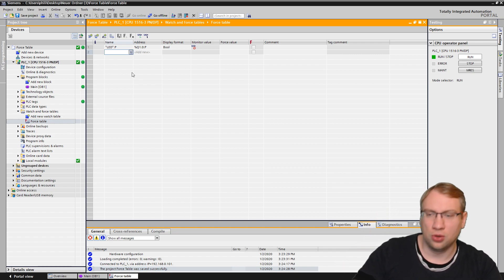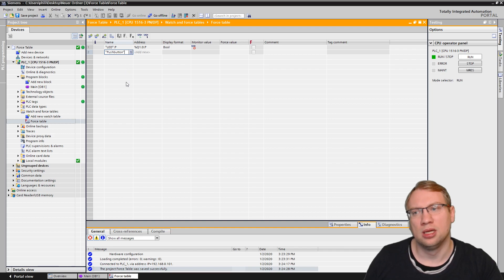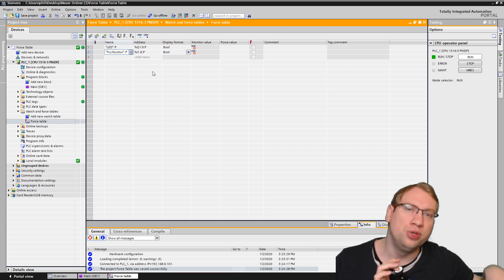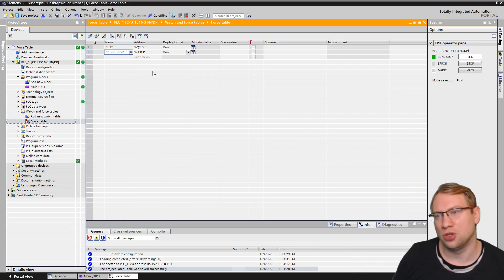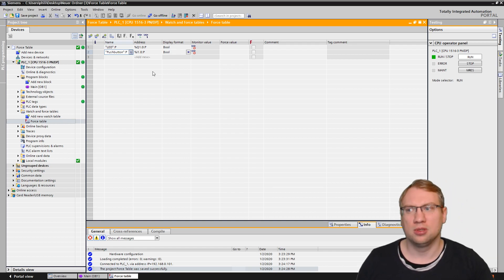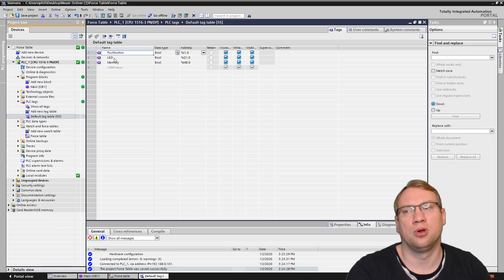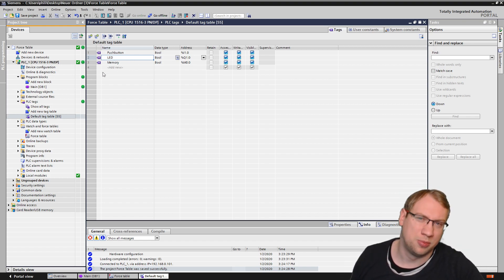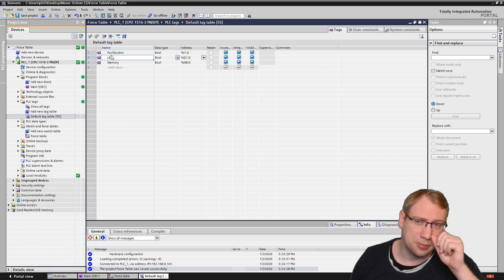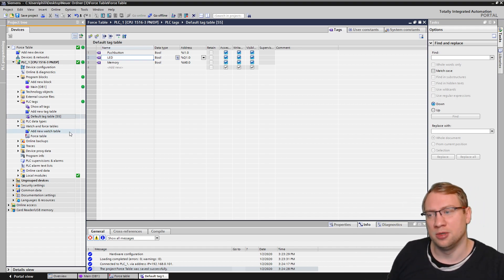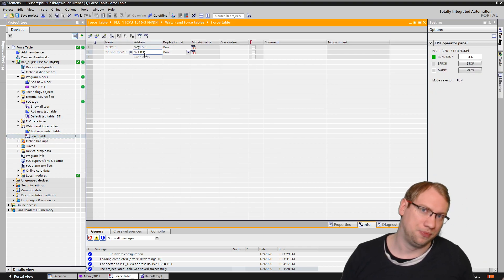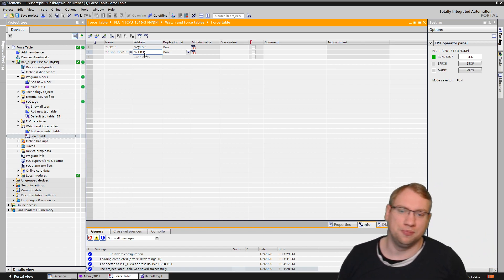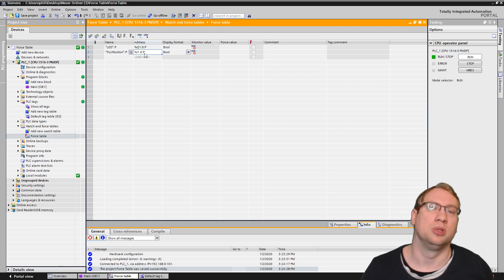It is so, so it is really like I am pressing the button. Like if I have the input, let's add the input here as well. If I have this push button, I press the push button. The 24 volt reach my PLC, the PLC LED goes on. The input indicator LED goes on and this is this peripheral input, right? This indicator LED in the program. In the program, we are then working, transferring this to so-called tags, right? To symbols, tags, variables. And those do not have this double point P anymore. So those are just internal in the PLC, looking into a cabinet, looking into variables, into memory areas. Because the force table does not look into memory areas, it directly accesses the hardware. It doesn't look into memory, it directly accesses the hardware.